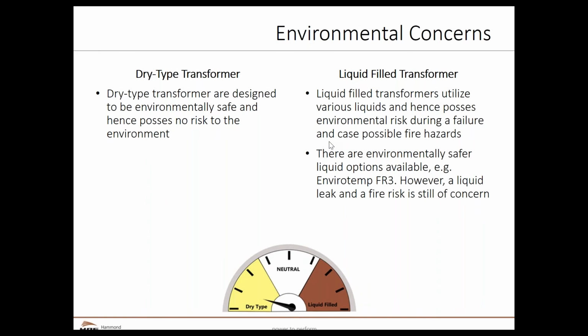Environmental concerns are an important and growing concern. Dry type transformers, for the most part, are environmentally safe. There really is no risk for a dry type transformer. We're not really concerned about anything when we install it in an environmentally sensitive area. Liquid filled, however, does present some problems. Depending on what the liquid is, some of the least expensive liquids would be more equivalent to, let's say, diesel fuel, or more commonly, at least in North America, mineral oil.